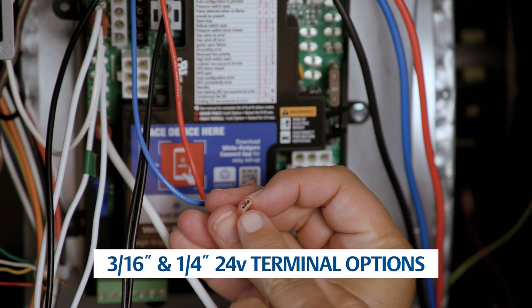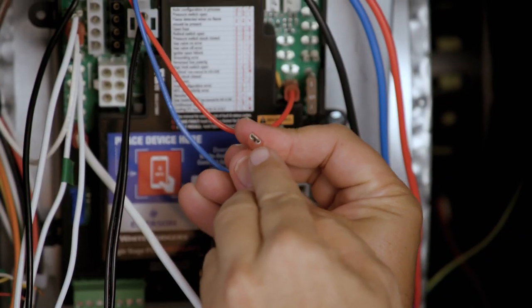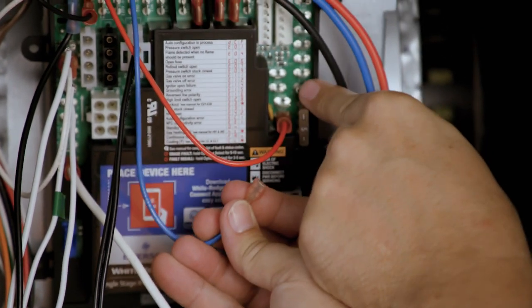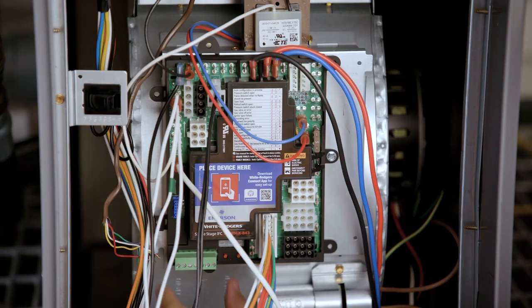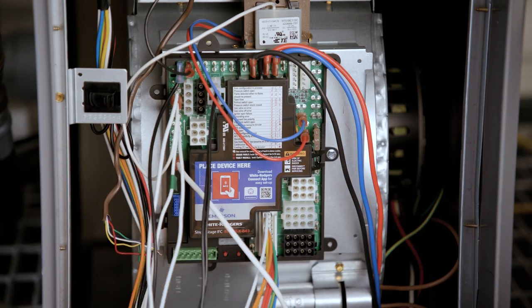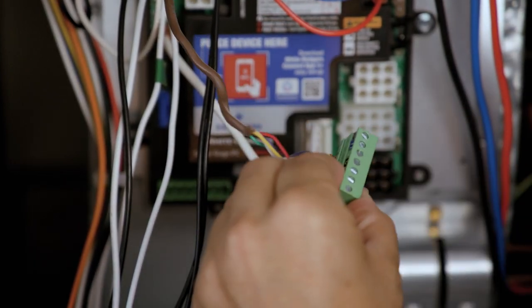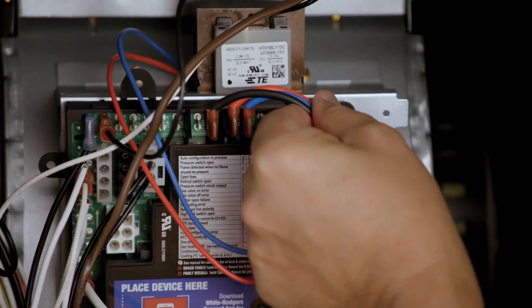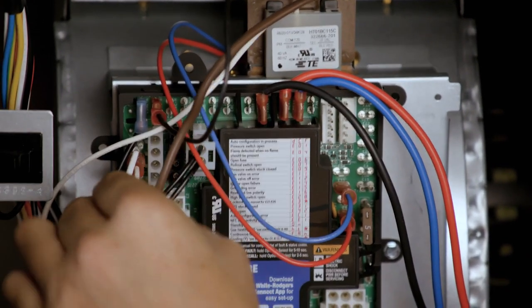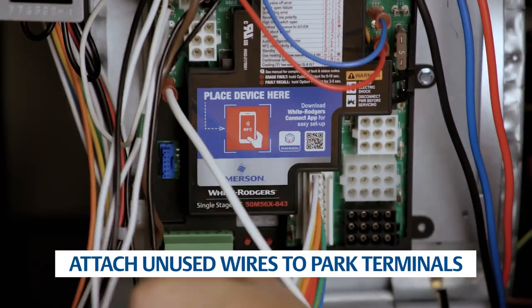Identify the correct spade size for the 24-volt hot and common wires and attach the transformer low-voltage wires to the correct terminals. Remove the thermostat bus block from the control and install the thermostat wires according to the terminals they were removed from. Then plug the block back into the control. Ensure all wires and connectors are secured to the control board and any unused blower speed wires are attached to the park terminals.